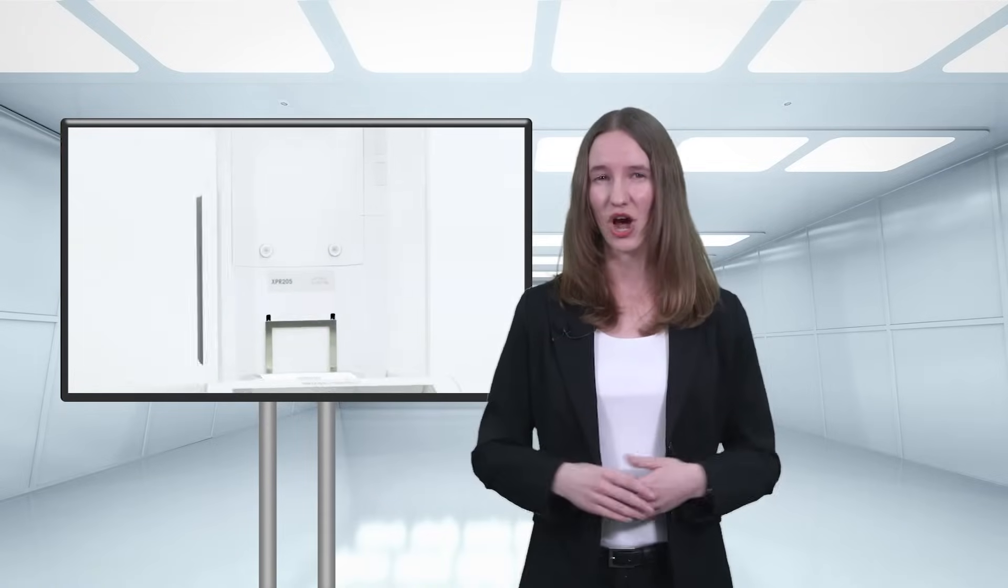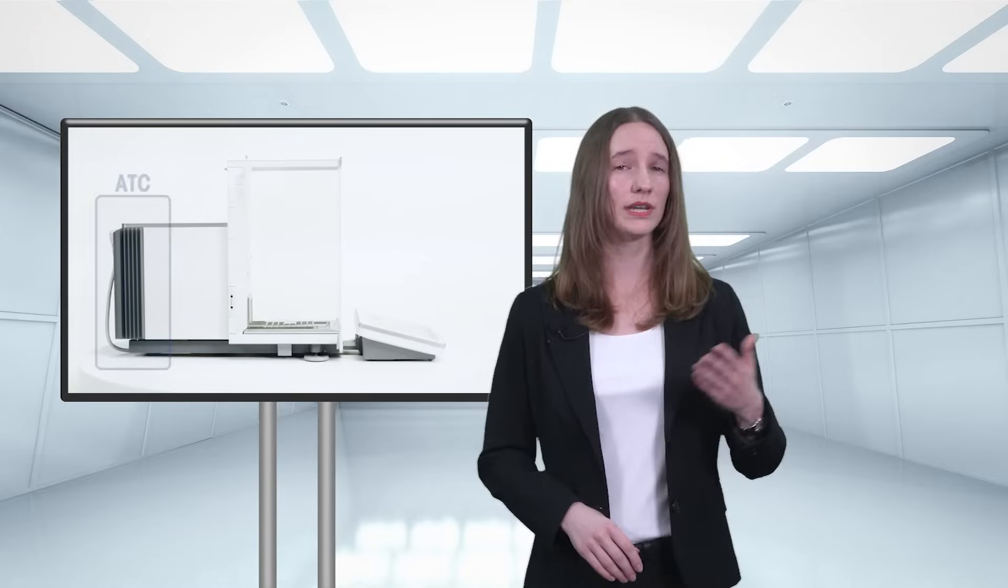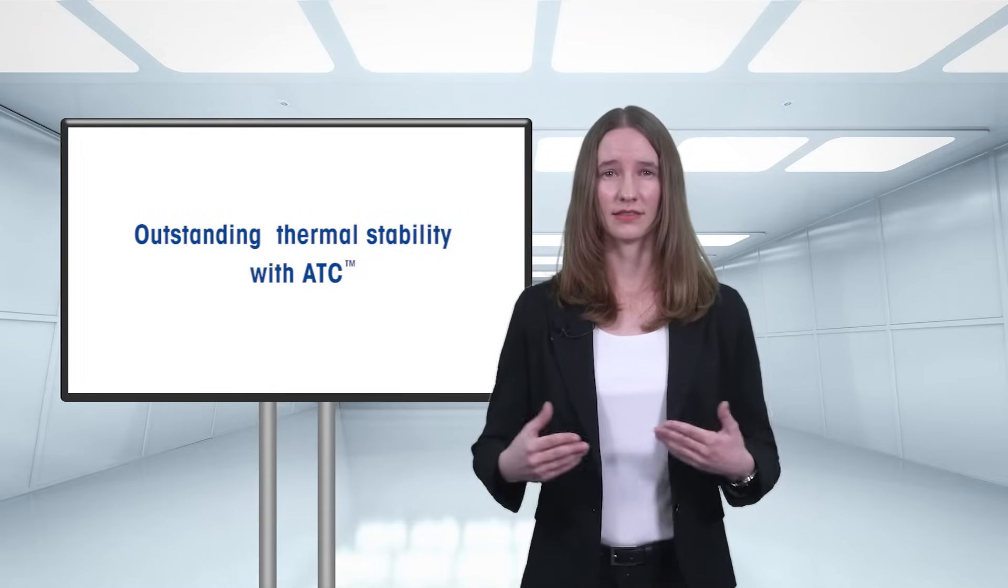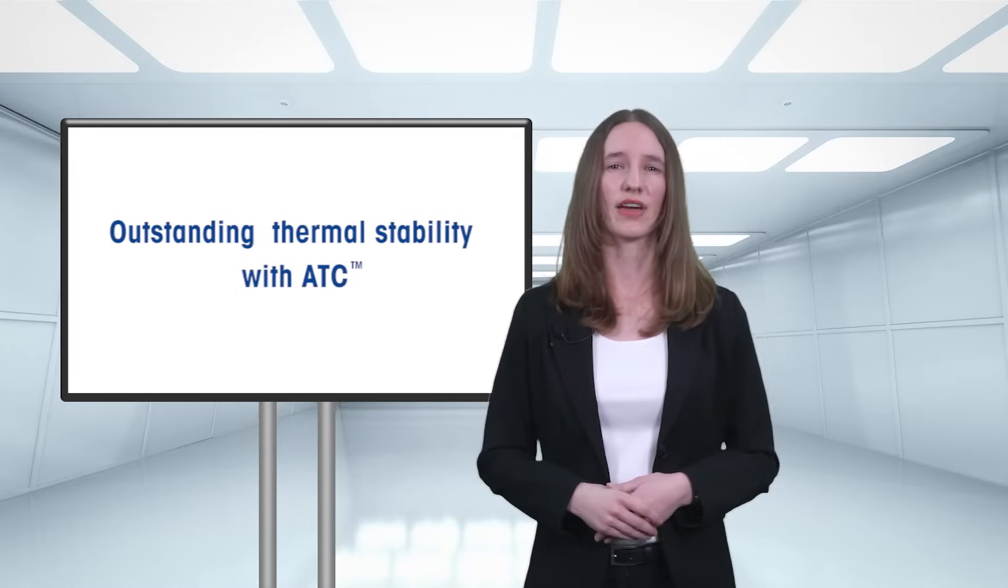How do we accomplish that? The first answer to this question is the intelligent active temperature control system that eliminates temperature differences between the weighing chamber and the environment. This technology significantly decreases settling times by mitigating convection currents and balance drift.